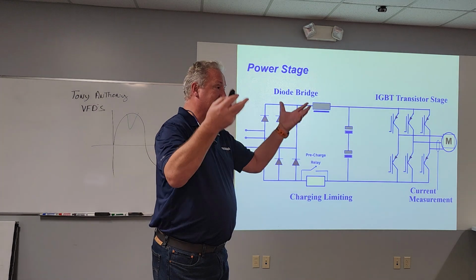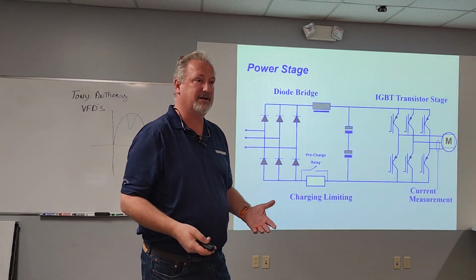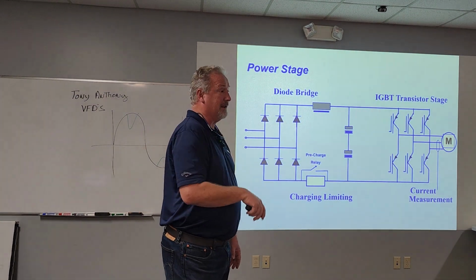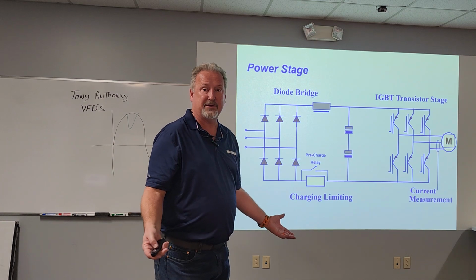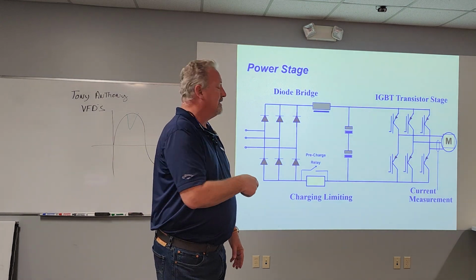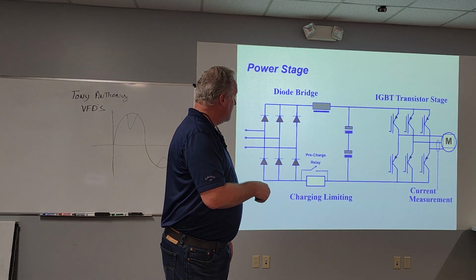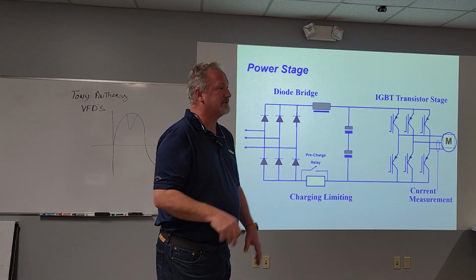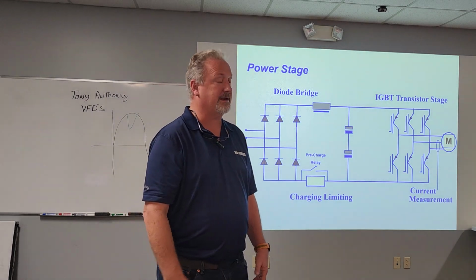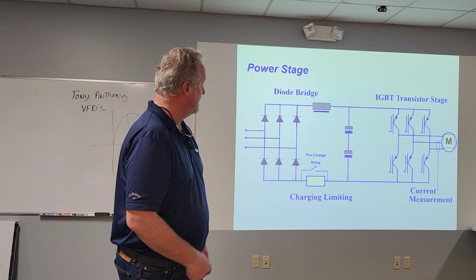And then once we get the DC bus fully developed and the capacitors fully charged up, we close that relay, because if we left that resistor in there, we'd never have power. We couldn't do anything. We need full power. So that's called the pre-charge relay. Once those are charged up, the relay closes and we take that resistor out of the circuit. And now we can have power.